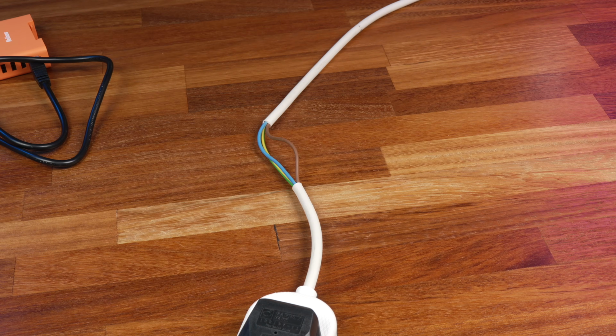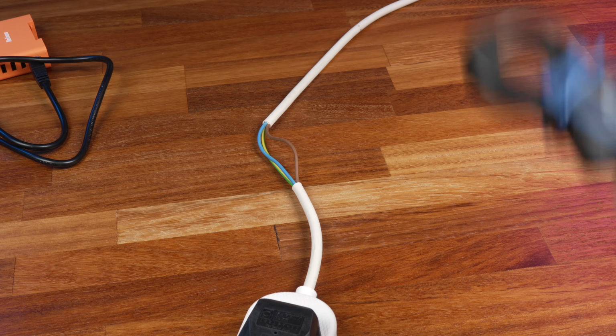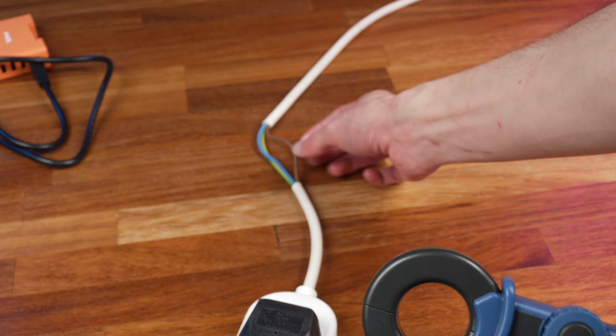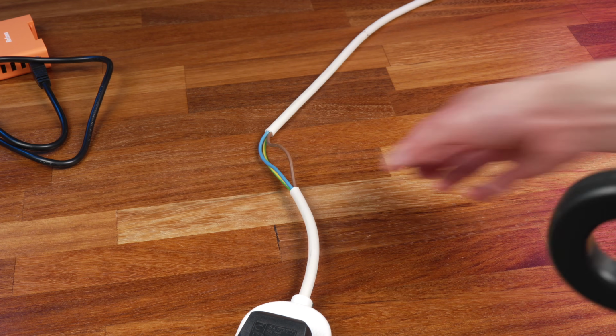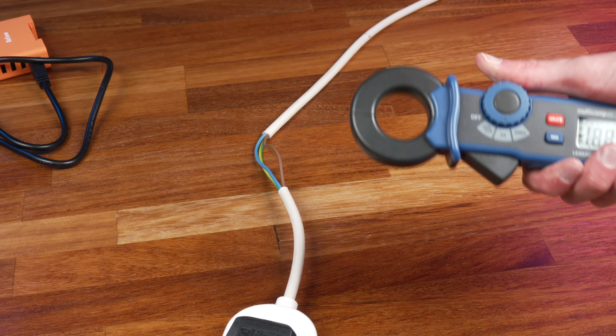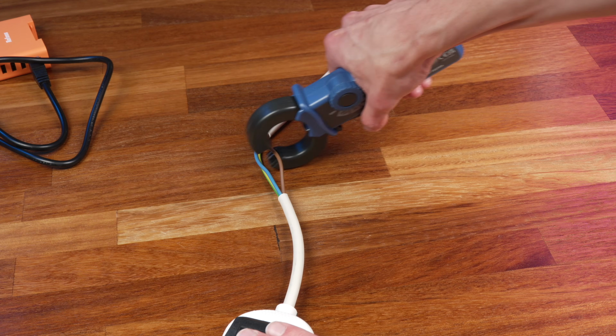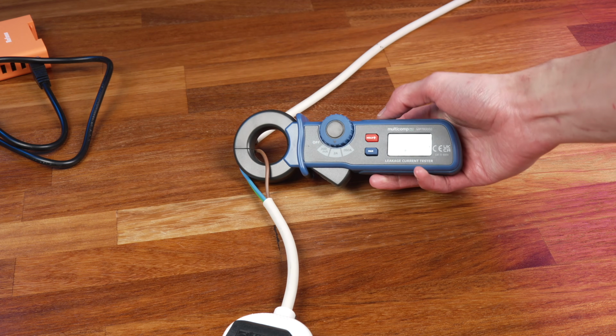So we've now got a load connected here and powered on, so now let's try measuring this. The first thing you need to bear in mind is you need to clip the CT around just the line conductor, not the line and the neutral, and not the entire cable. So if we take the clamp meter here and we turn it on and we clamp it just around the line conductor, so just around that wire there, we can see that we're measuring the current.